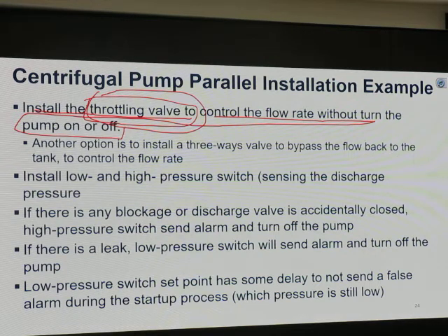Okay, but if we close it all the way for a centrifugal pump, and the pump is on, is that okay? It is. Still okay, and it is preferred to start it with the discharge valve closed. So to start the centrifugal pump, we close the discharge valve, we let it run, and then we open it. We will go over that in the water flooding facility that Mr. Gulak will cover. For the PD pump, if I did that, it's going to be a disaster.